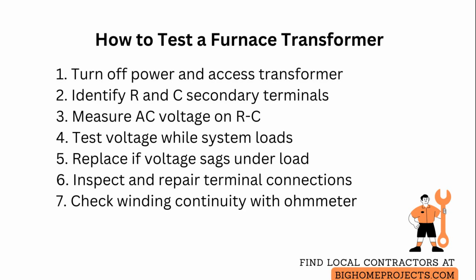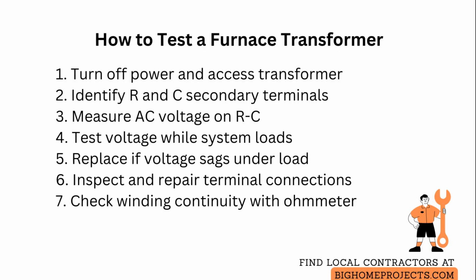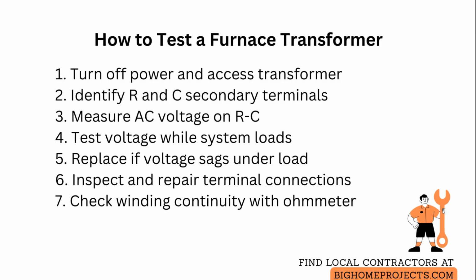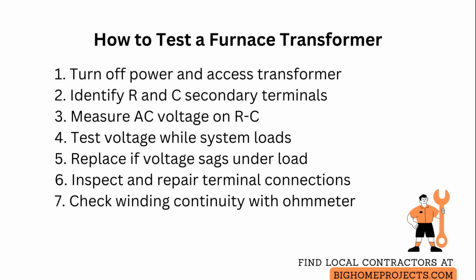A healthy transformer will read near the rated secondary voltage, often 24 volts, under load, while readings well below that or zero indicate overload or open secondary. To test under real load, energize the system so that the gas valve or relay coil draws current. Measure voltage while the load is applied because an unloaded measurement can be misleadingly normal.